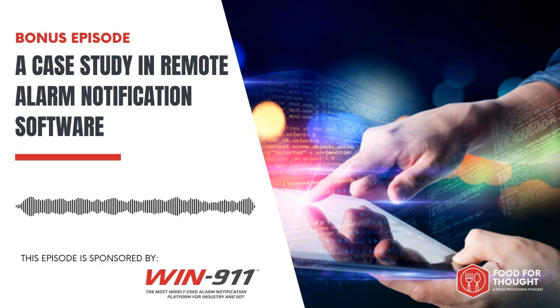Absolutely. We run into issues with monitored water level, flow, pressures, etc. throughout the year, but oftentimes it's our precursor alerts that we're able to set based on key performance indicators for our sites. We can basically utilize the remote monitoring and remote notifications to identify when we have a sentinel event, something that we're looking for, whether that be drought or low pressure. And so, for example, we've had a number of instances where we've had a relief valve fail, and immediately we get a low pressure in a pipeline, and we get a remote notification almost instantly by text or within a couple minutes via email, and we're able to respond to the site, make the appropriate adjustments, or initiate field repairs as soon as possible.